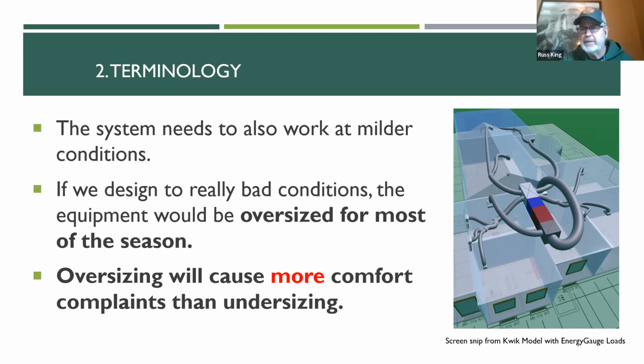You never reach the full efficiency of the equipment, and it blows really cold air, and it makes stratification within the house worse and things like that. So oversizing is actually a bigger problem than undersizing in terms of comfort complaints and energy efficiency at the same time. It's human nature to want to round up a size just to be safe on your equipment. You should actually be doing the opposite. You should be looking for opportunities to round down a size and have your system actually be smaller, which is more appropriately sized to the load calculation.